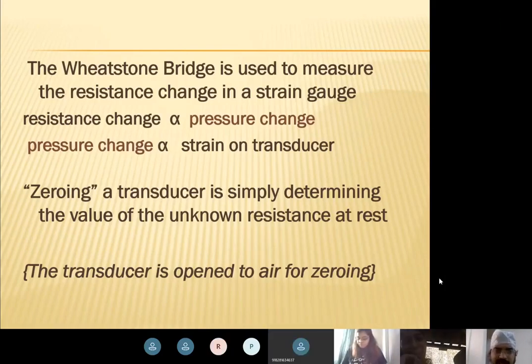You run around to optimize the scale, but you don't run around to zero the line again. Zeroing the line again doesn't make any sense. You've already zeroed the line. You don't need to zero it 10 times. Okay, so once you decide to put in an arterial line, the first thing you do is zero the line. Before you put in the arterial line, you first zero the transducer.